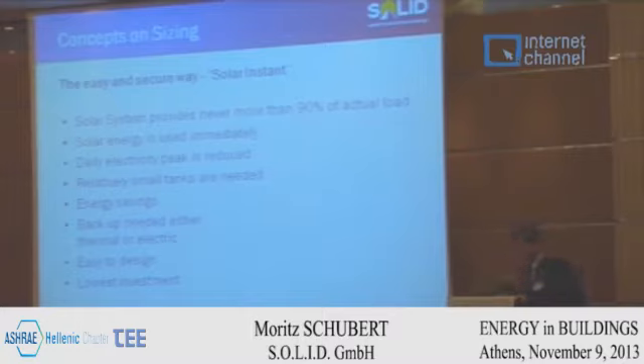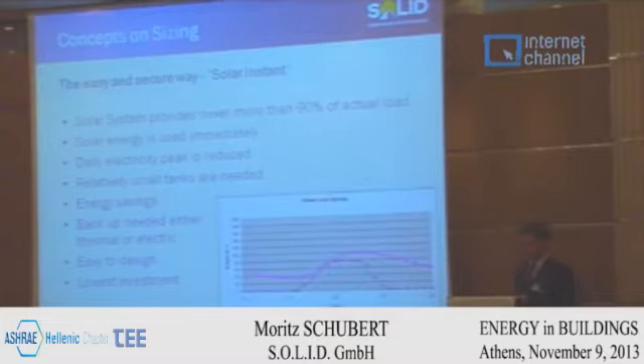Now I will present you a few concepts on sizing a solar plant. There's this concept we call solar instant. We don't have a big heat tank, so the heat generated by the solar collector field directly drives the absorption chiller machine. When the sun is shining during the day, you have cooling from the solar cooling system. But in most countries you want to have the cooling running into the evening also. So if you have enough space for a larger solar cooling system, you go for the other approach, which I will show you now.